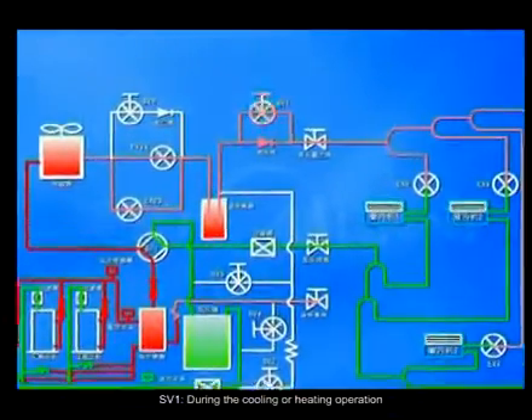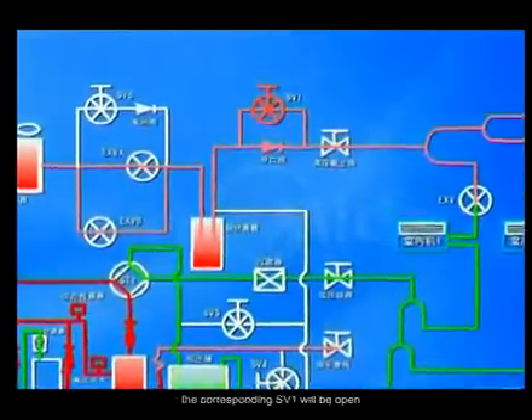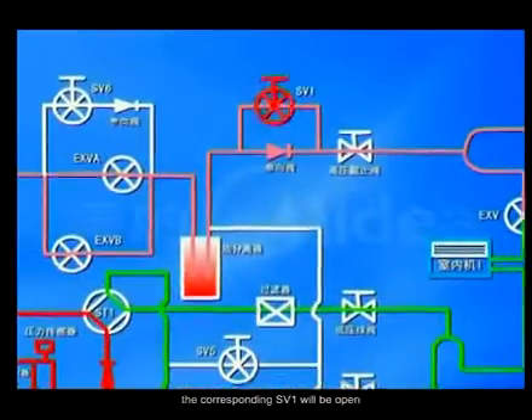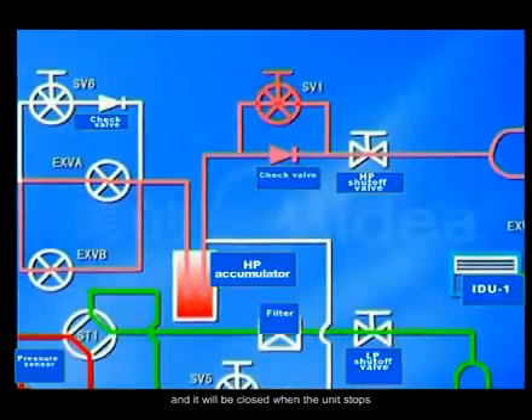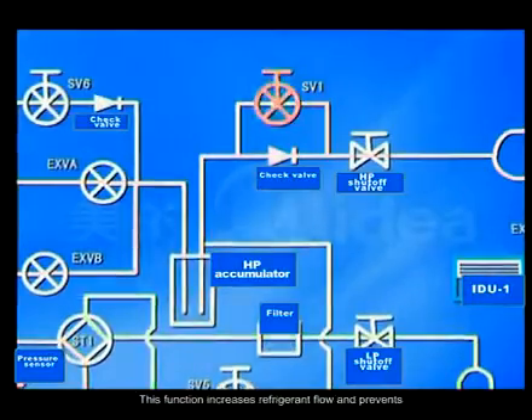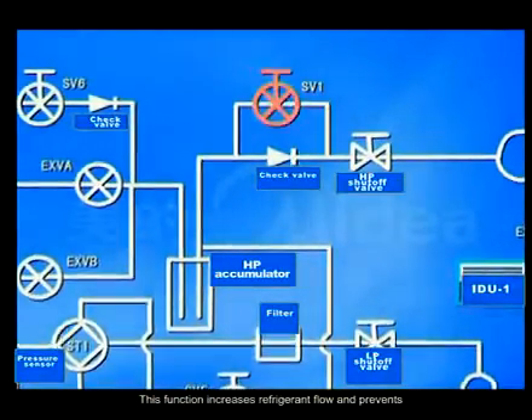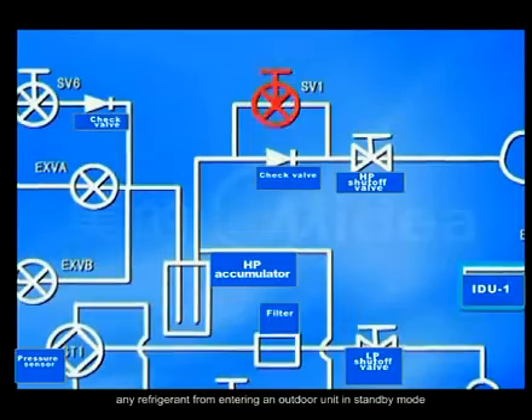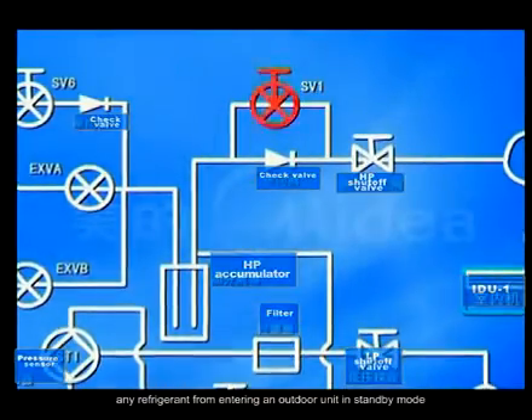SV1. During the cooling or heating operation, the corresponding SV1 will be open, and it will be closed when the unit stops. This function increases refrigerant flow and prevents any refrigerant from entering an outdoor unit in standby mode.